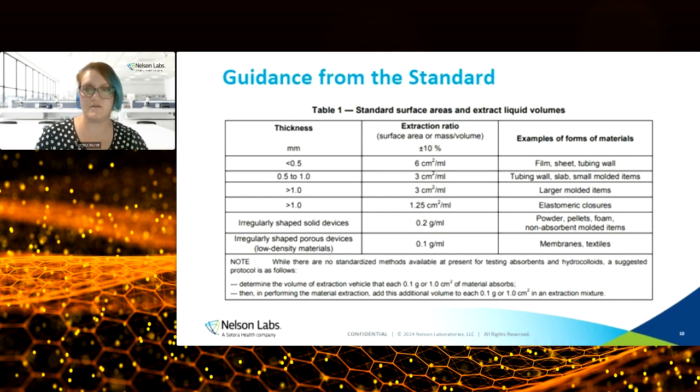Yeah, and Katie, you bring up a good point with making sure that we're testing the worst case. And I know in a previous slide of mine, I said to exclude the non-contacting areas. The reason for that is because when sponsors have given us samples along with the surface area, they actually accounted for all those non-contacting areas as well. And so that means that with a higher surface area, there's more test extract.